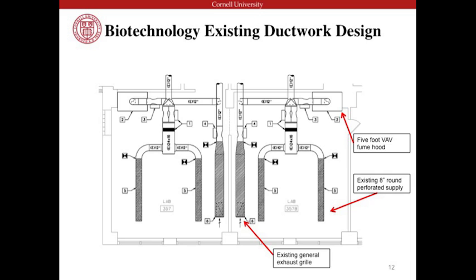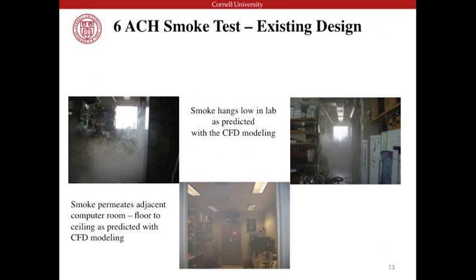So this is kind of a time lapse. At 7 minutes, the smoke is really still staying by the ground, at 12 minutes, and then finally at 20 minutes it's finally cleared out. So it took about 20 minutes for that lab to clear out, with no visible smoke. This is a bit of a blurry picture, but this was at the 6 air change rate.